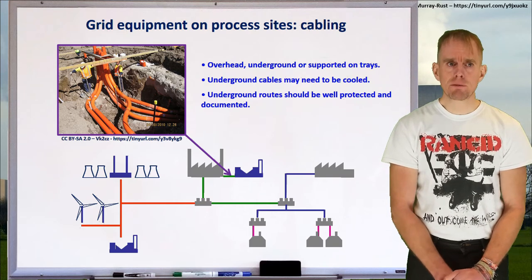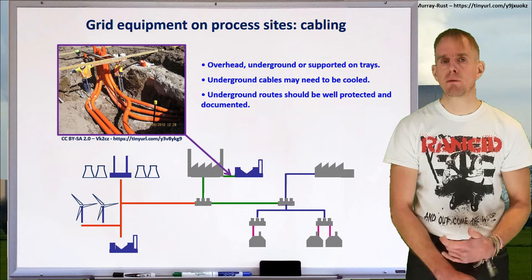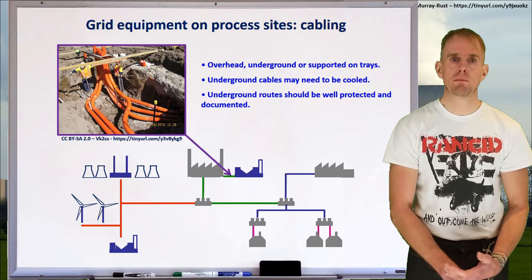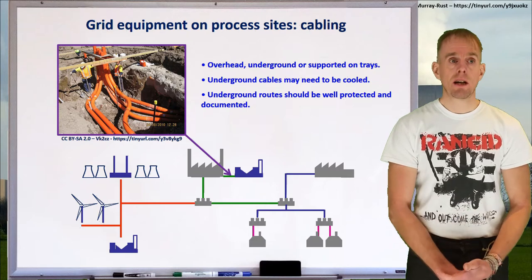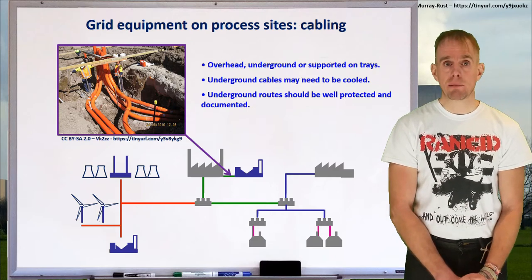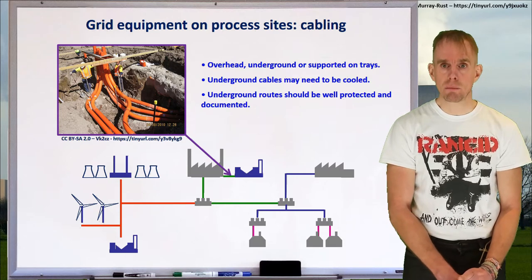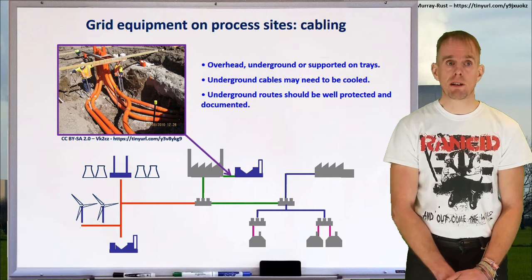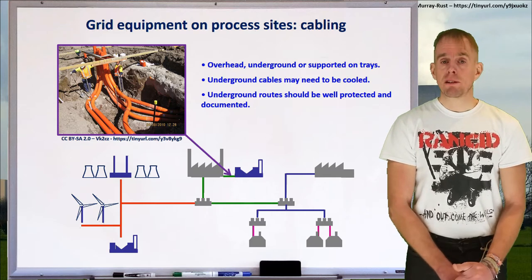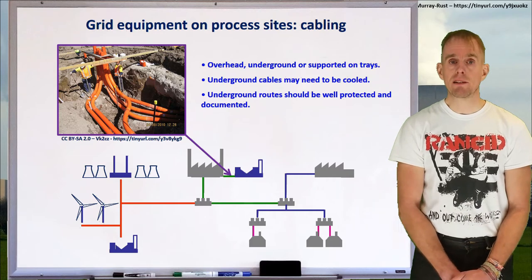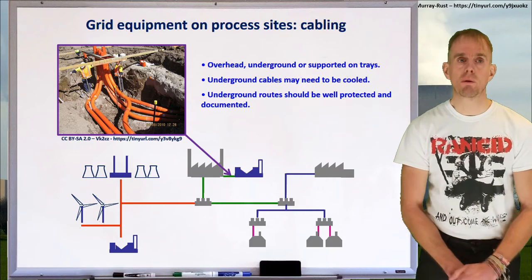But first of all, if there's any underground cables, they need to be incredibly well protected and well documented, because the last thing you want to happen is for some contractor to come along with a digger and start digging into the ground to do something and cut a main power feed. Not only would it destroy the digger and probably the person in it, but it could also involve catastrophic loss of power to your site. Underground cables, depending on the load, may also need cooling, so that's an additional consideration that needs to be made at the choice of underground or overhead.